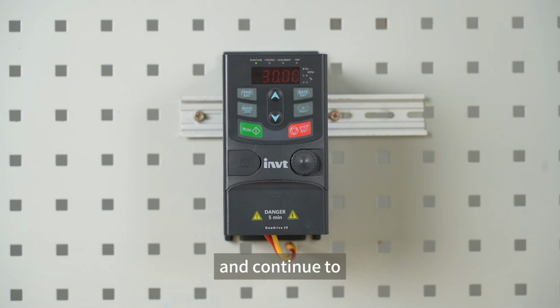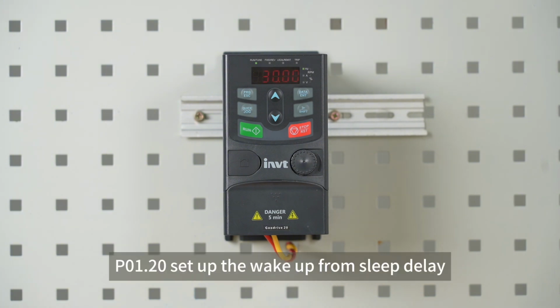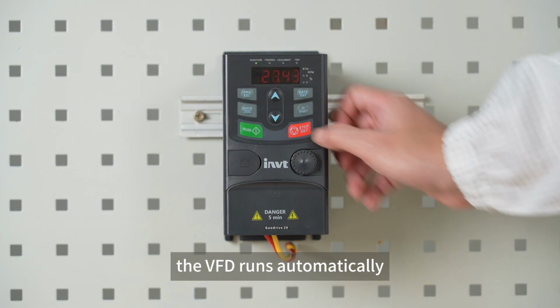And continue to P01.20, set up the wake up from sleep delay. The VFD runs automatically.